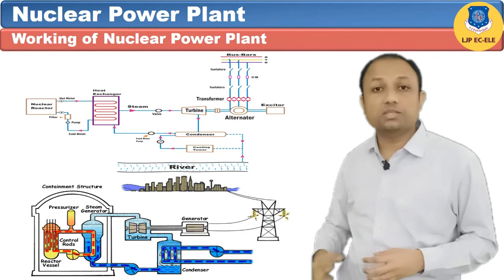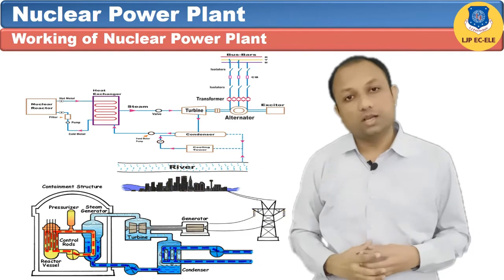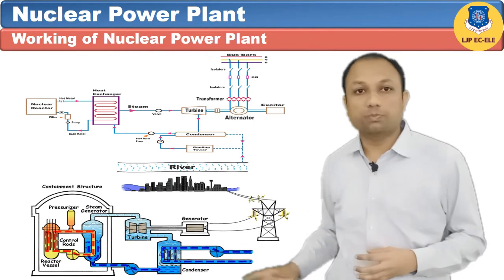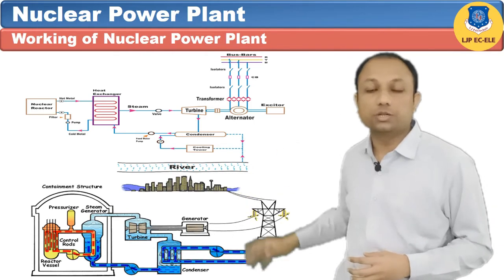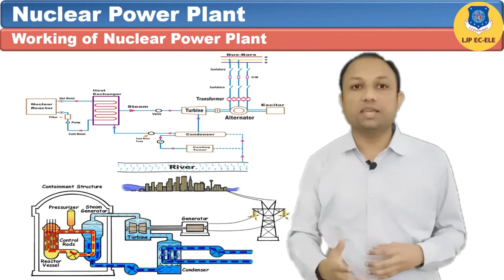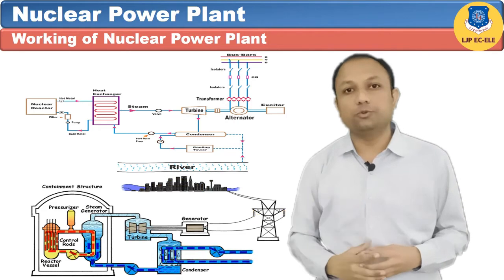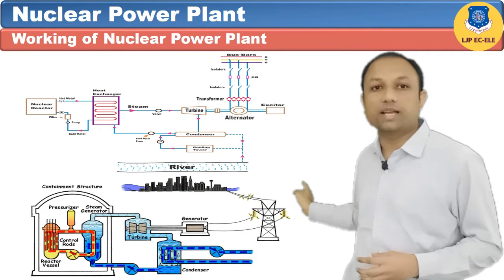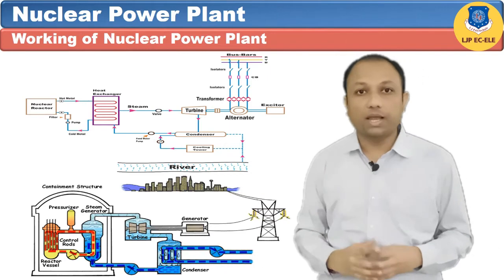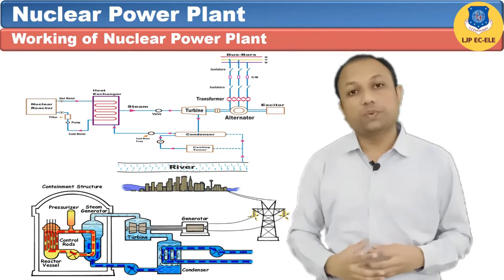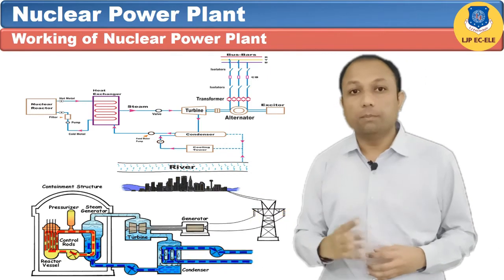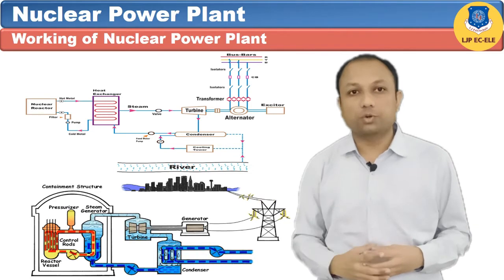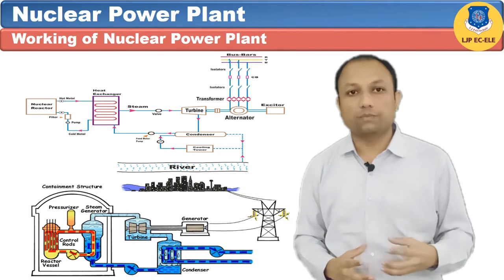Steam coming out of the turbine is taken to the surface condenser. Cooling water is passed through the tubes of the condenser, so the steam is condensed and converted into water. This water is taken out by the condensate extraction pump and is fed to the feed pump.